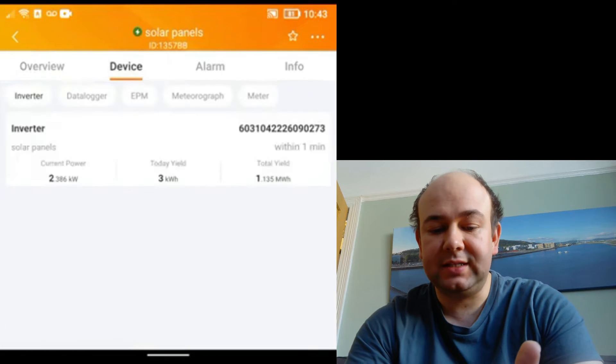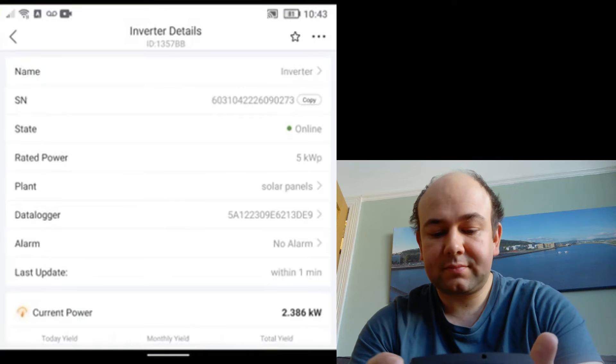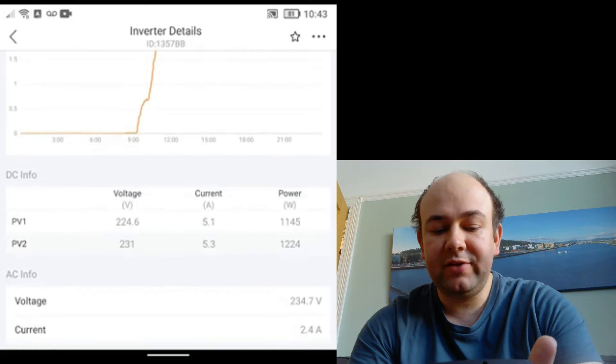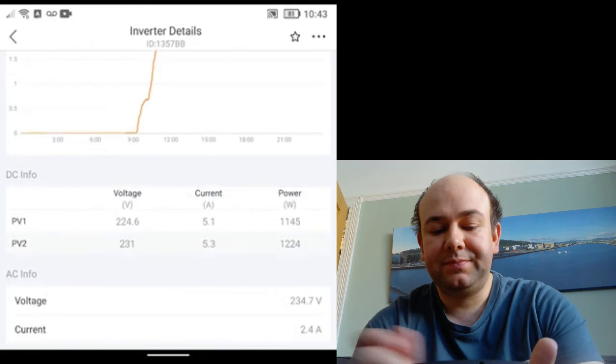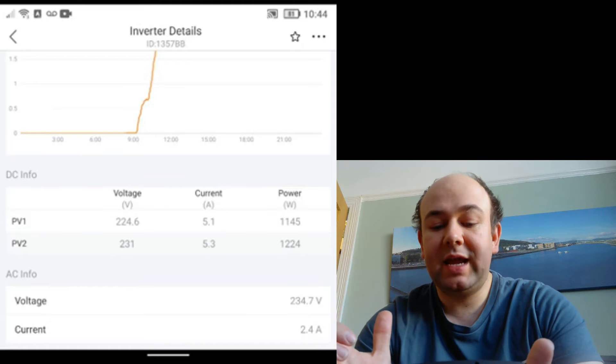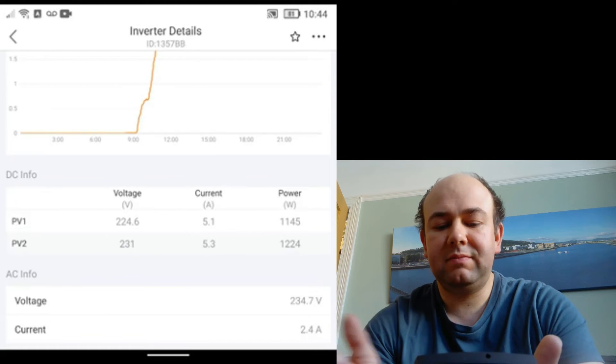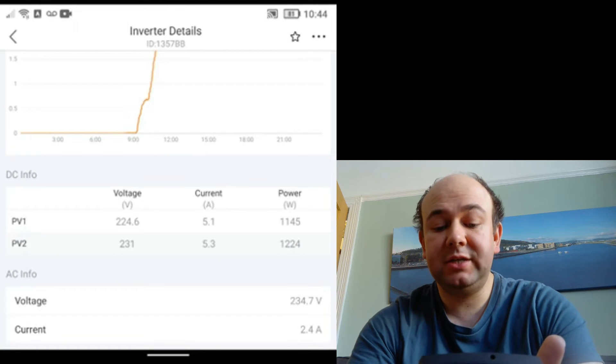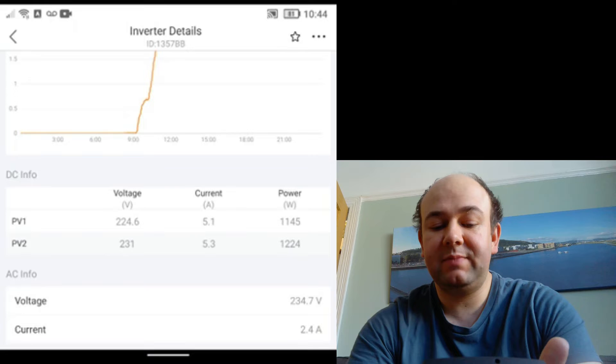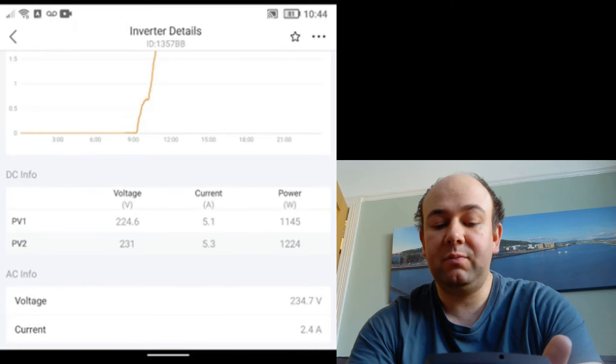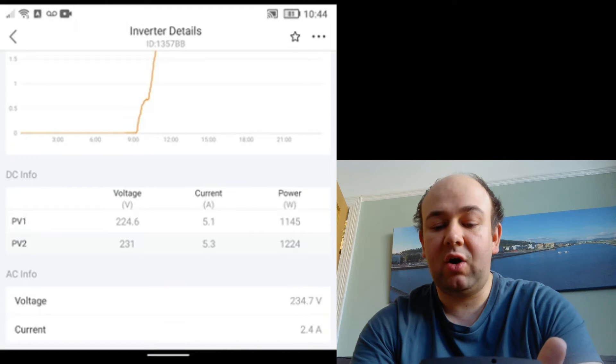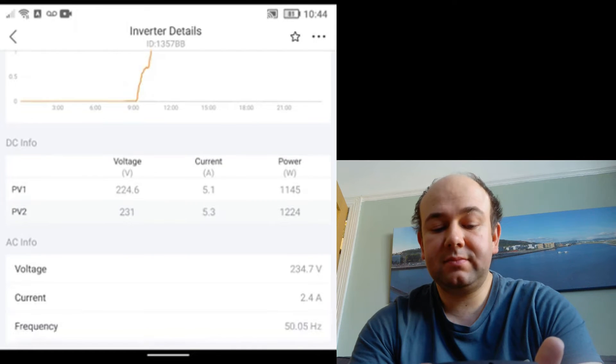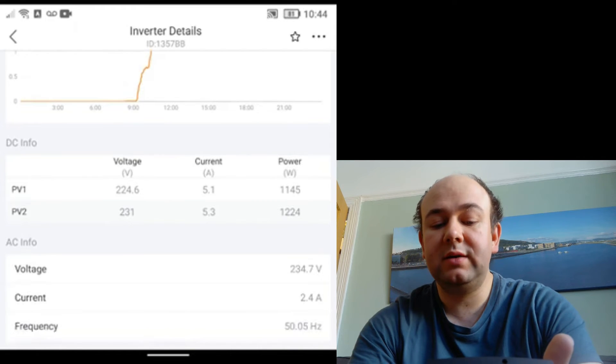Again we've got that graph that we saw on the other side of our generation, but below this we have PV1 and PV2. My system is set up so we have two strings of six panels going into the inverter, so this shows what each string is producing. So each six panels, you can see one string of panels is operating at 224 volts, producing 5.1 amps, and that's a power of 1145 watts. Well, number two is at 231 volts, 5.3 amps, and 1224 watts.